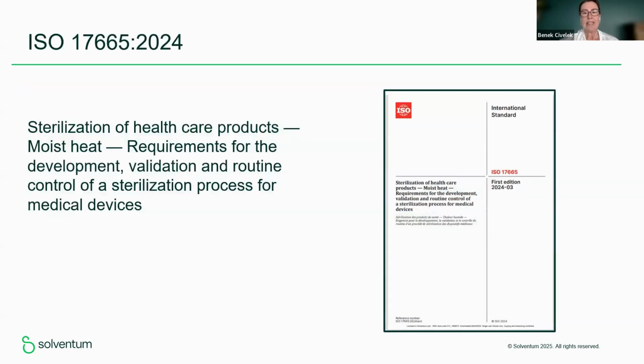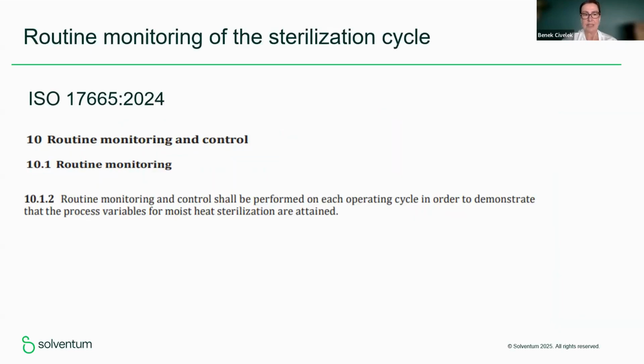I am also active in standard committees, which is TC 198, the Sterilization Mirror Committee. And ISO is working very hard on updating the standards. One of them, which has been published recently, in 2024, is ISO 17665. This is important for CSSDs because it tells us all about moist heat, which we use the most inside the CSSD. And it covers the requirements for the development, validation, and routine control of sterilization processes for medical devices. So this is the steam sterilization standard.